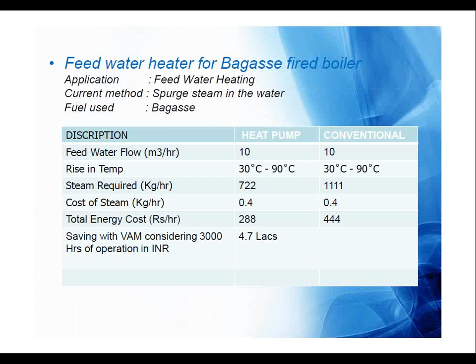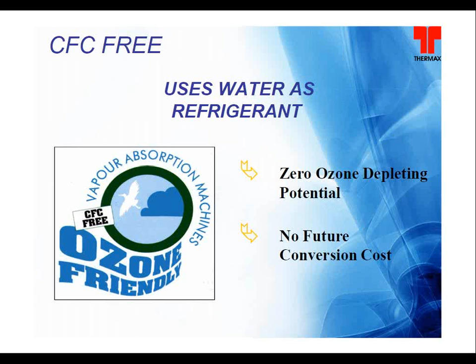And the same heat pump is also applicable for 80% depreciation benefit in the first year. As it is also a lithium bromide water cycle, there is no wear and tear, and the refrigerant is pure water, so again it has zero global warming potential. There are no CFCs involved, it uses water as a refrigerant, so there is zero ozone depleting potential.